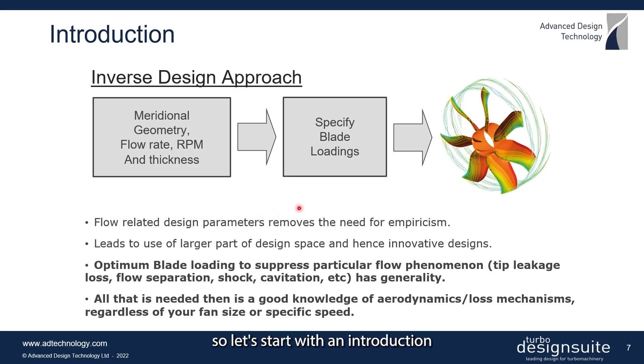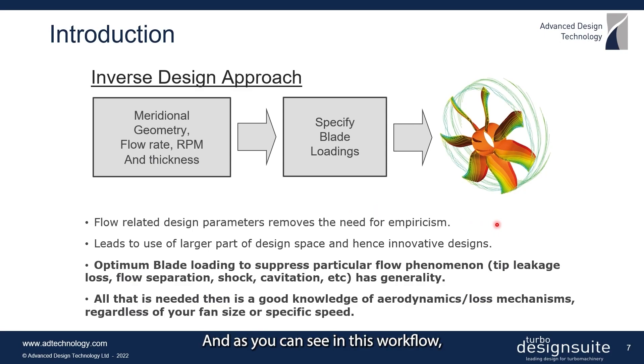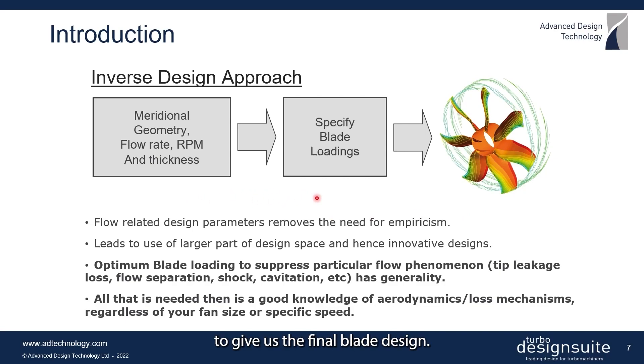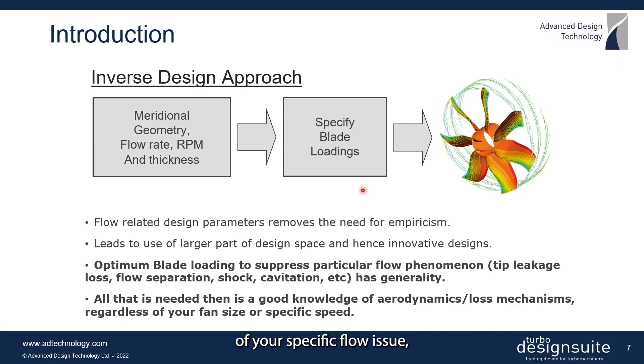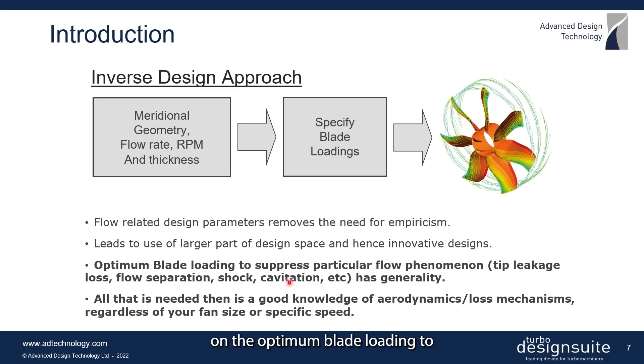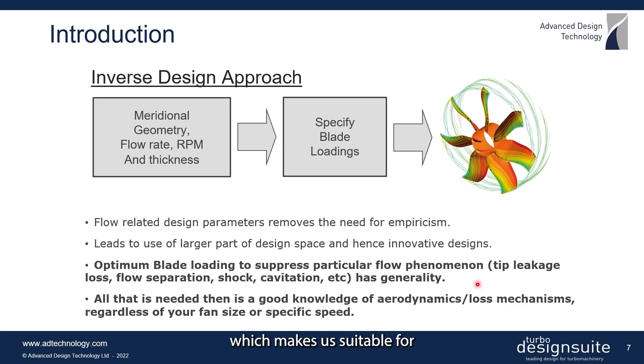Let's start with an introduction to the idea behind the inverse design approach. As you can see in this workflow, these are the inputs used by the inverse design method to give us the final blade design. Apart from some basic parameters, these blade loading inputs are flow-related. Once you have a good understanding of your specific flow issue — whether it's tip leakage, profile loss, or flow separation — it's possible to come up with guidelines on the optimum blade loading to tackle each of these issues. This know-how has generality, making it suitable for all axial fan applications.